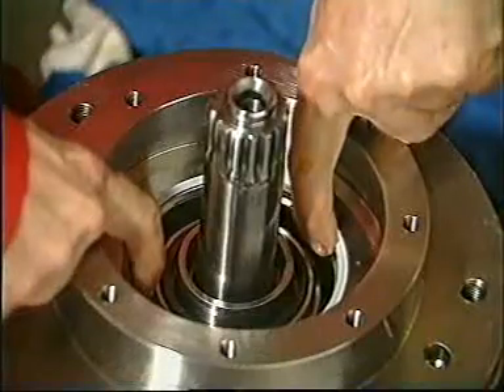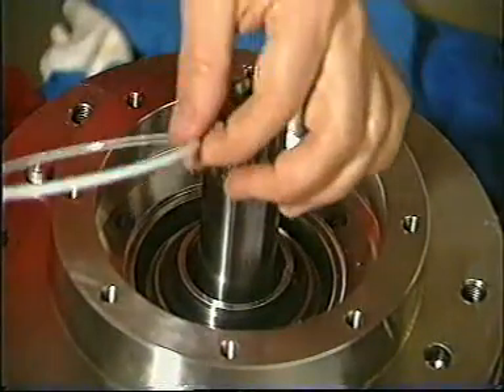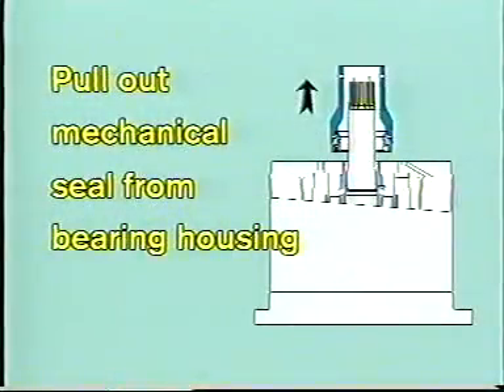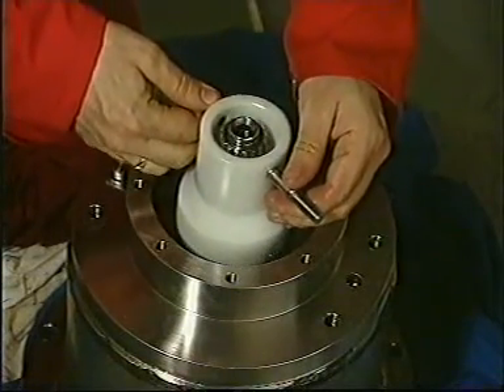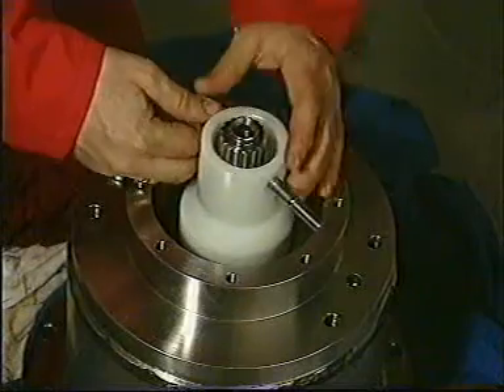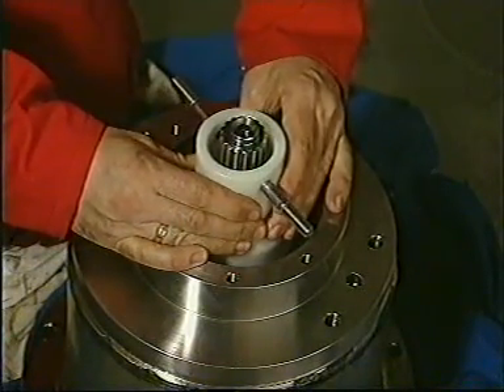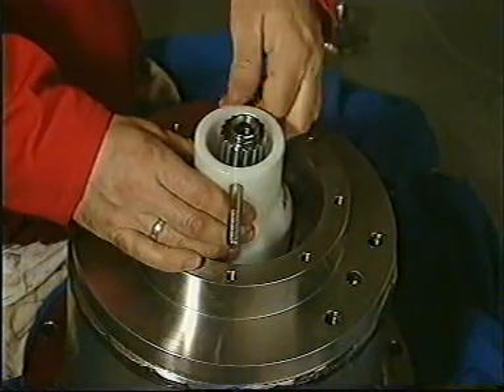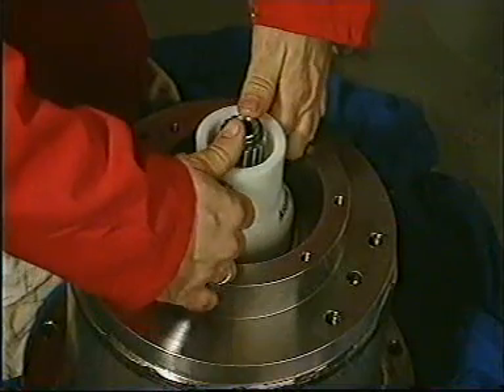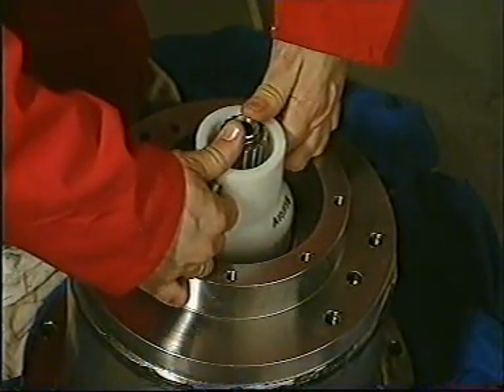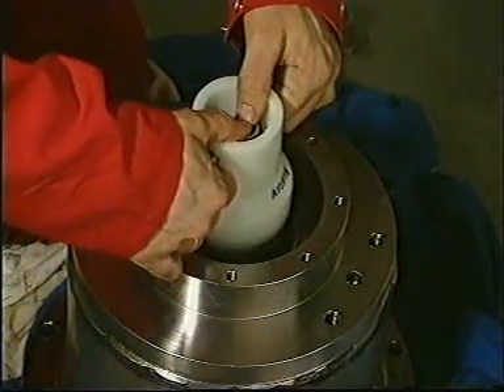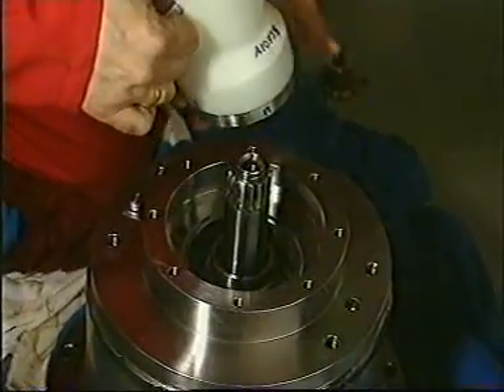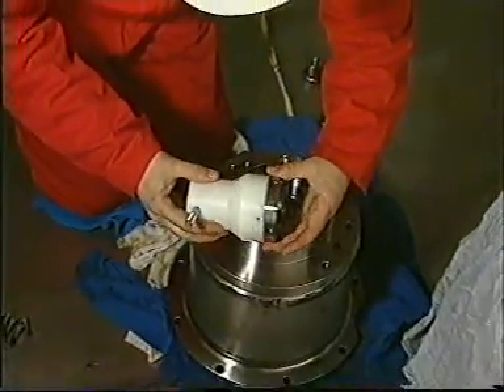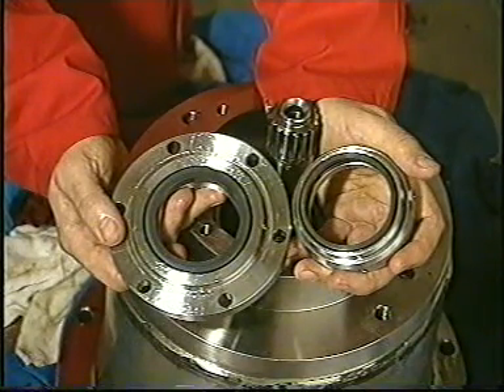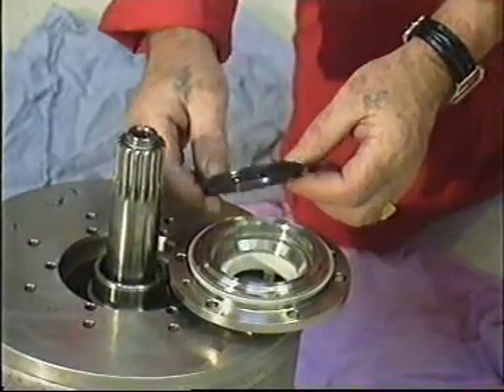Carefully control the stationary part of the mechanical seal and the Teflon seal element. Pull out the rotating part of the mechanical seal by using the special tool from the Framo toolbox. Pay special attention when twisting on the tool for lifting out the seal's rotating parts. Control the seal face carefully. If the seal faces are destroyed, with fretting or grooves in the surface, they normally can be reconditioned. Remember, never use grease on the O-ring on the stationary seat.